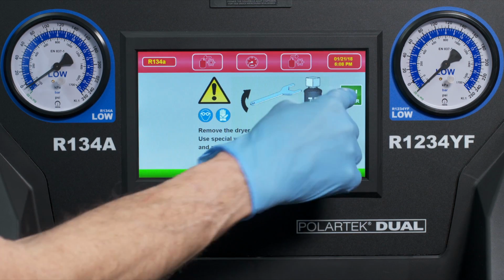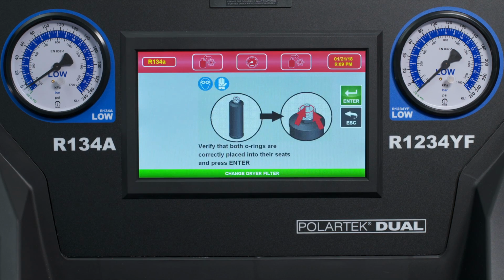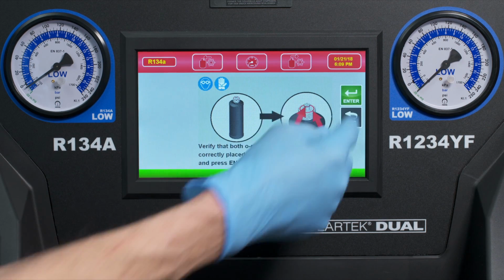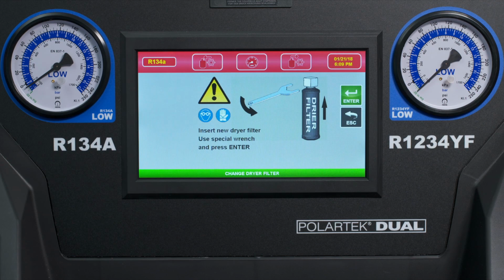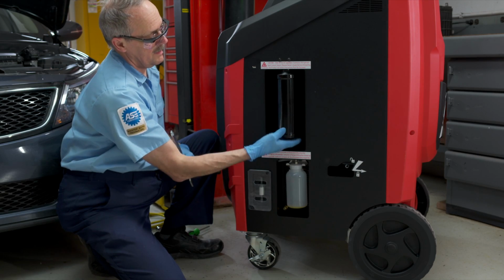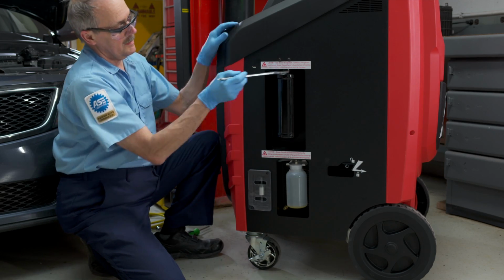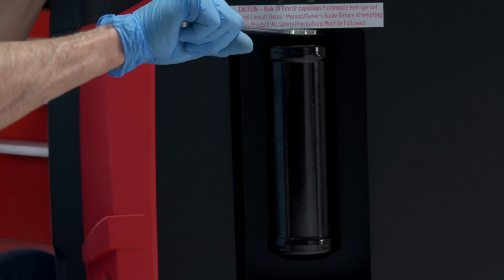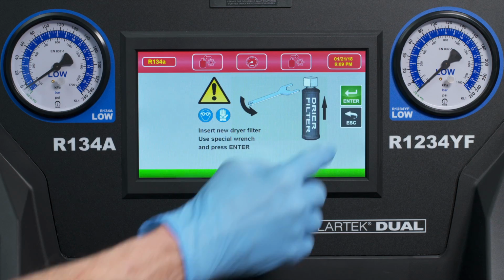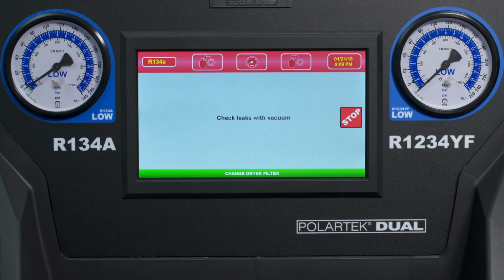Hit Enter. Then the machine will ask you to verify that the filter O-rings are seated correctly. Press Enter. Thread the new filter onto the machine and tighten with the wrench, as shown. When complete, press Enter. The system will check for leaks. Hit Enter to return to the main screen.